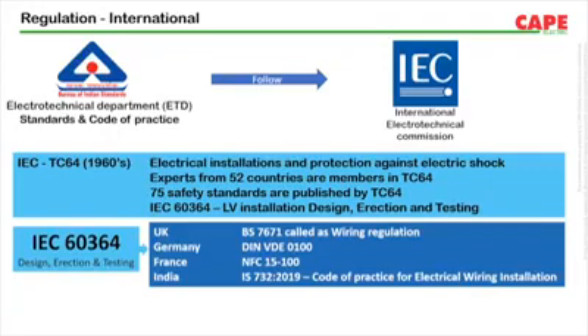The big change in India is IS 732 4th edition, published during February 2019, which is adopted from IEC 60364 up to part 6 of this IEC standard. So now our IS 732 is also a modern electrical safety standard which shall be followed as a rule for design, erection and testing of an electrical installation up to 1000 volt AC and 1500 volt DC.